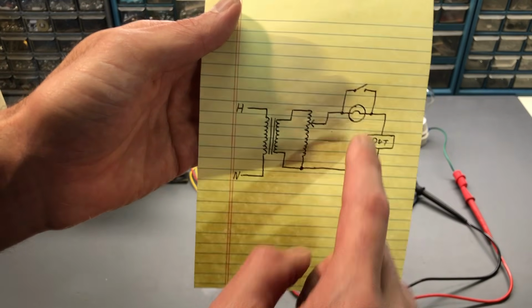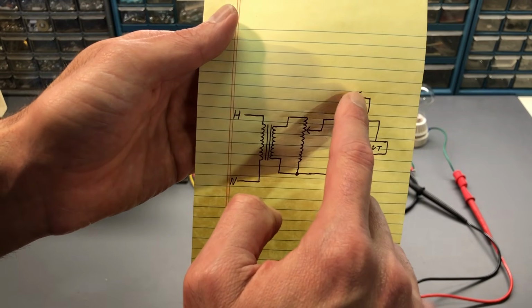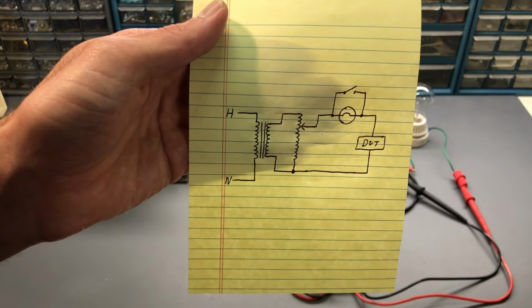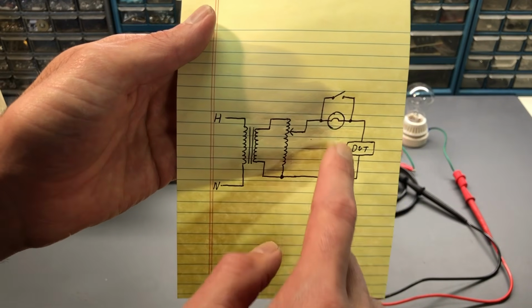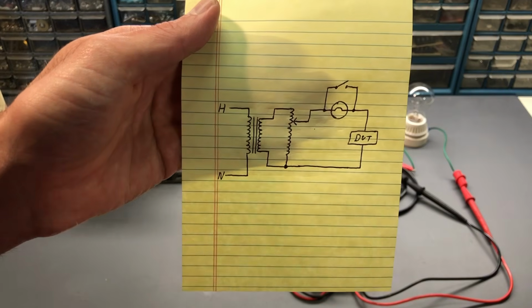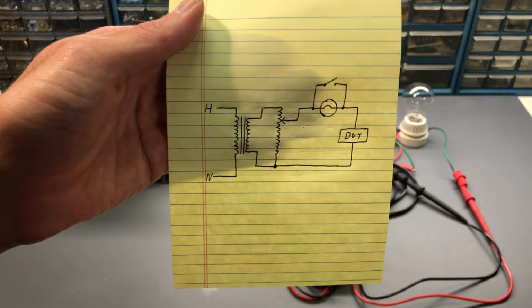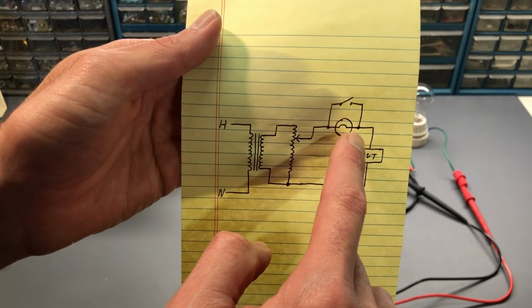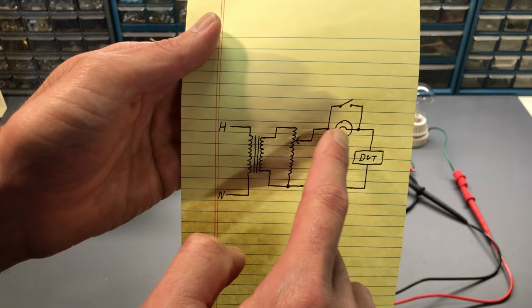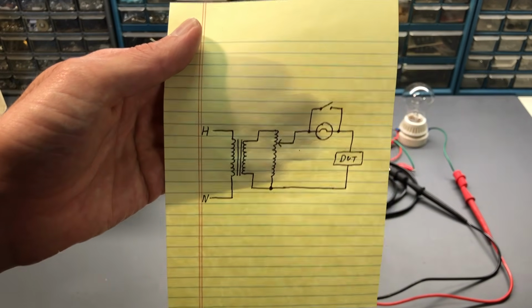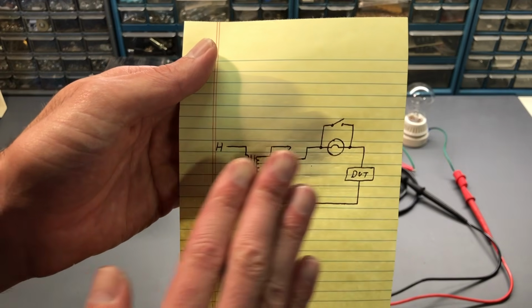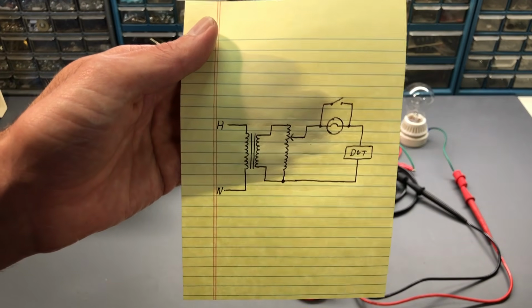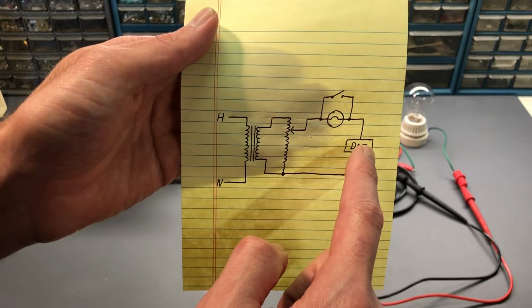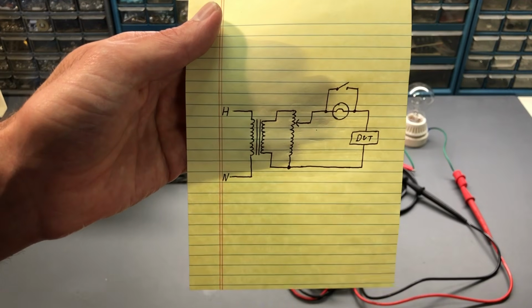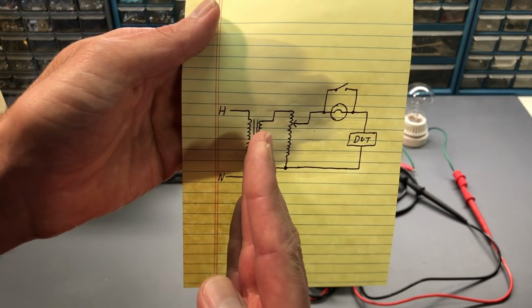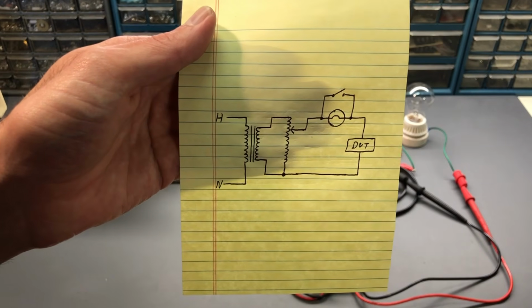All right, now I did draw the switch right here. This is a switch that I previously showed on my setup where I can bypass that incandescent bulb, that little switch box with the bulb on top of it. When you close this switch, it shorts out the bulb and you have no current limiting. So it's very, very important to remember that when that switch is closed, in no way do you have any current limiting in this setup. But that's useful for being able to apply full line voltage to the device that you're testing. And again, you're isolated, but you're able to have that full voltage applied to it.